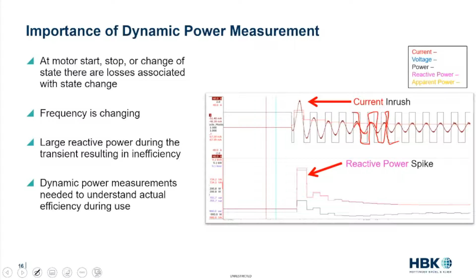With this we can see that at the beginning there is a large reactive power during the transient, resulting in inefficiencies, because nobody wants reactive power. So where does the reactive power go? It becomes heat. Dynamic power measurements need to be there to understand the actual efficiency during the use of the machine.